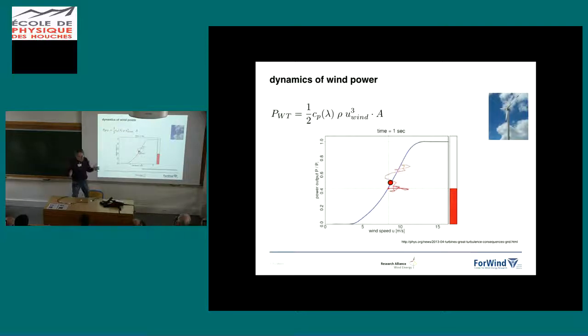If I look at a wind farm, and this is interesting, I see 20% of the farm ramping up and down in a few seconds. I'm working on this - there are interesting synchronization effects, collective effects of the wind park, which in my opinion are all stupid. If I show this to the manufacturers, they say, okay, what the hell, we have to handle this, but they haven't found a better control system. They tried, but there's misunderstanding.